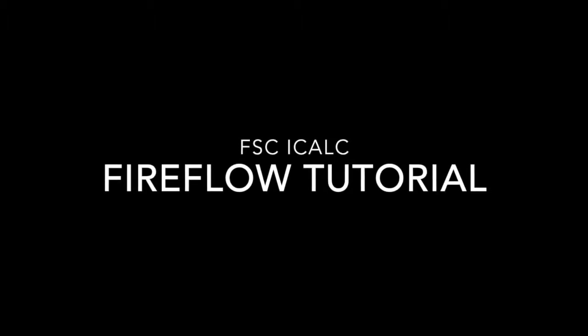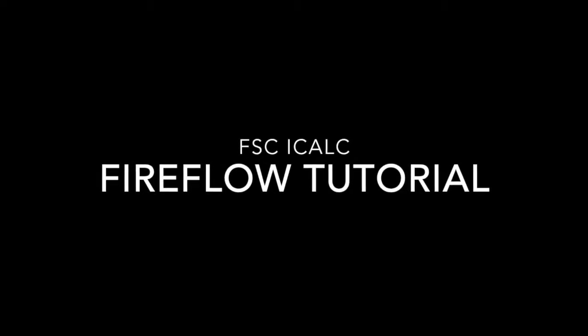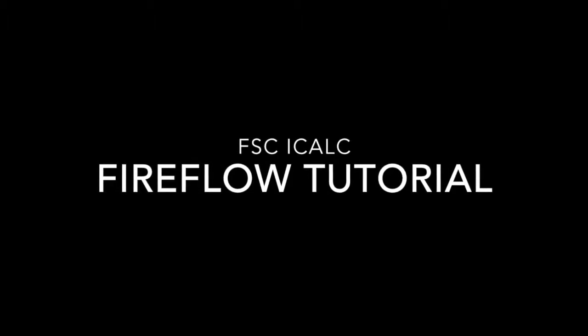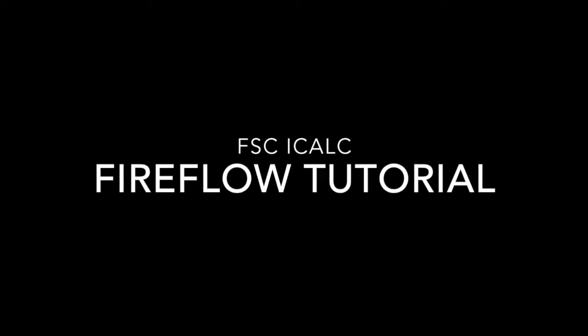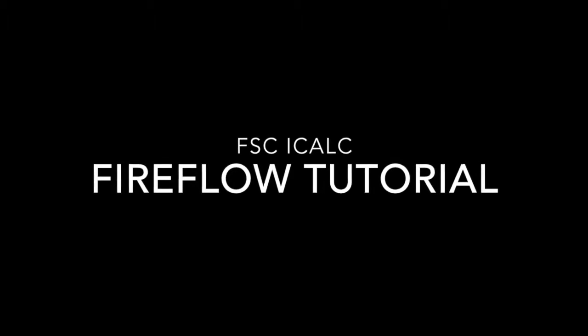This tutorial covers the iCalc FireFlow applet, which determines the required amount of water for firefighting, not fire sprinklers, and the duration of water supply per the IFC. FireFlow is only to be used if the sprinkler demand is less. If the sprinkler demand is greater than the FireFlow, then it should be used instead. This figure will ultimately depend on many factors and may be adjusted by the AHJ, so be sure to clear with them what exceptions and adjustments they will choose to accept or not.